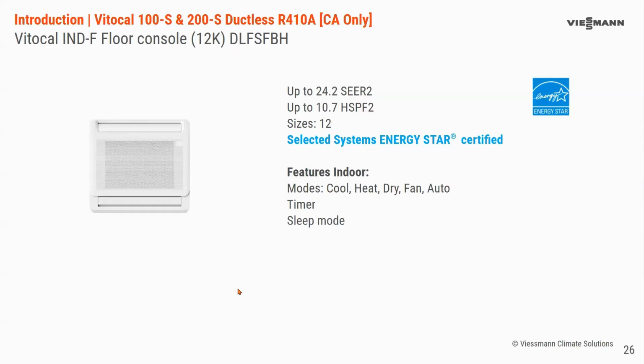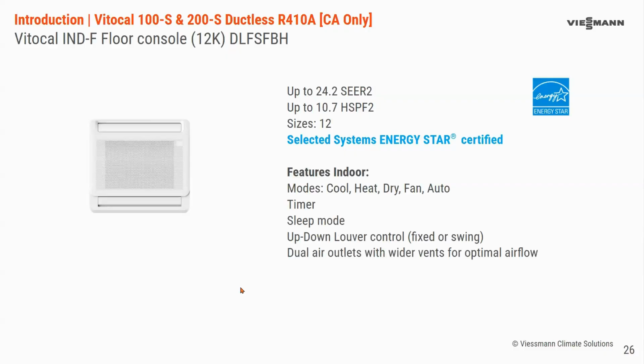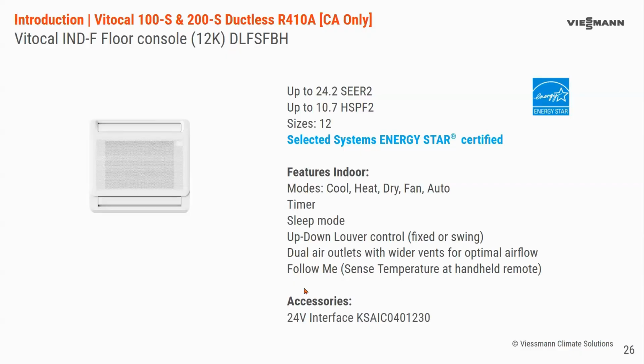Standard modes: cool, heat, dry, fan, auto. You have your same louver control, fixed, swing. This does have dual air outlets, top and bottom, that you can control independently as well. The remote control still has the follow me sensor feature, and you have your 24-volt accessory on this indoor unit. Standard with the wireless controller, optional with a wired controller. This is a good option for a radiator type installation, baseboard installation if you're replacing one. That's really where we would see these used more.